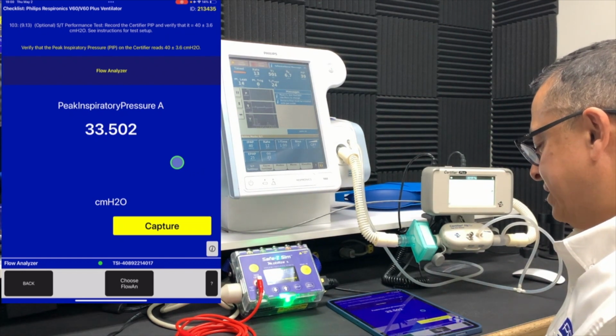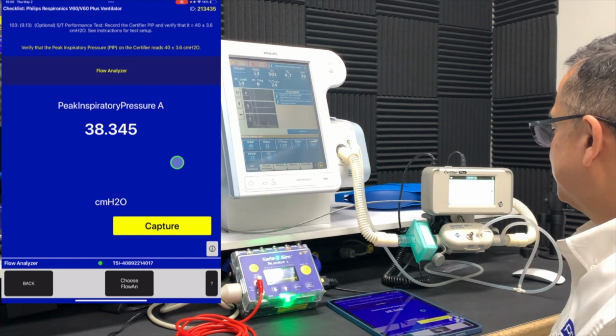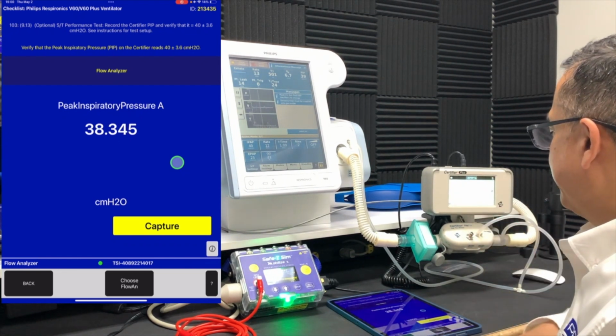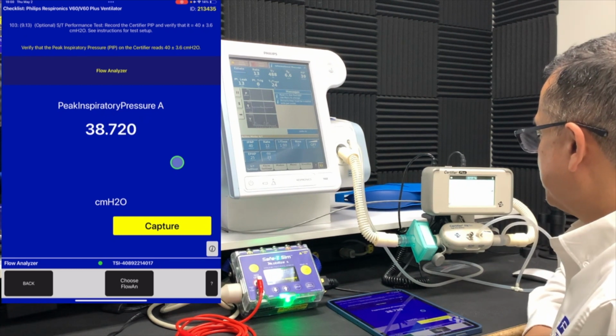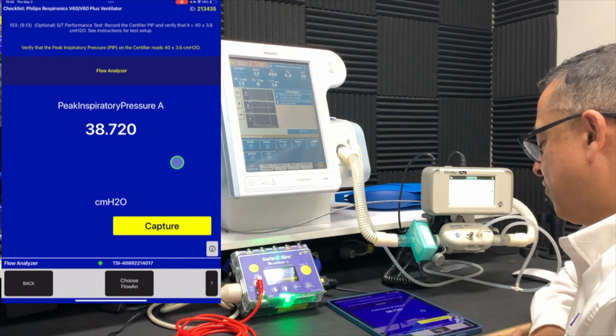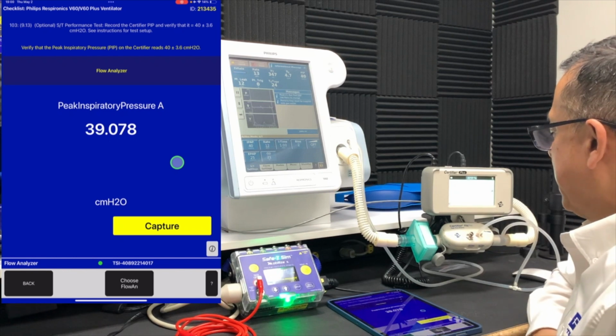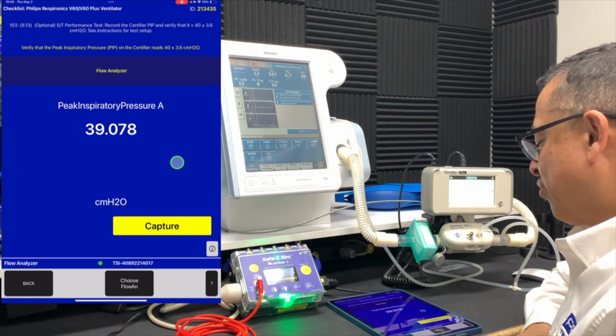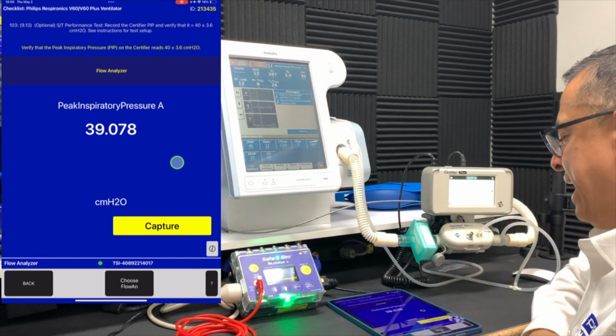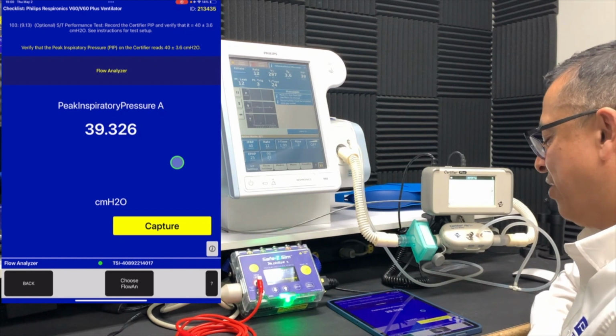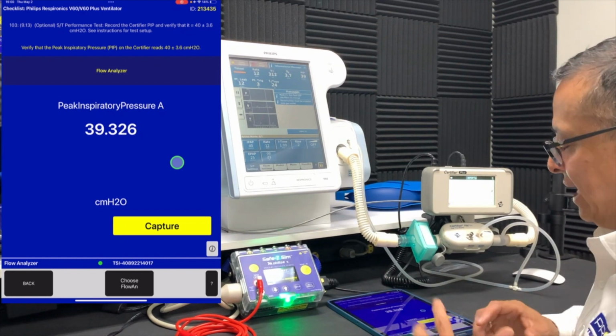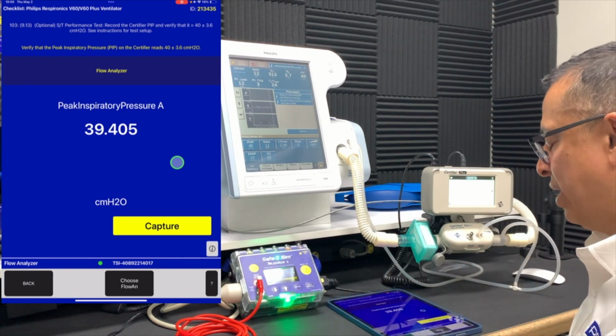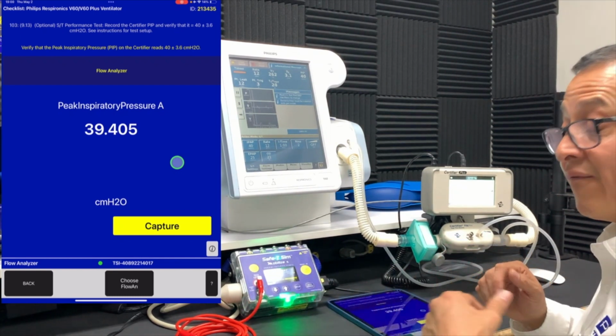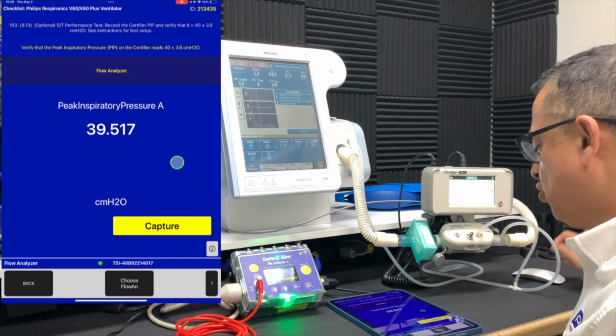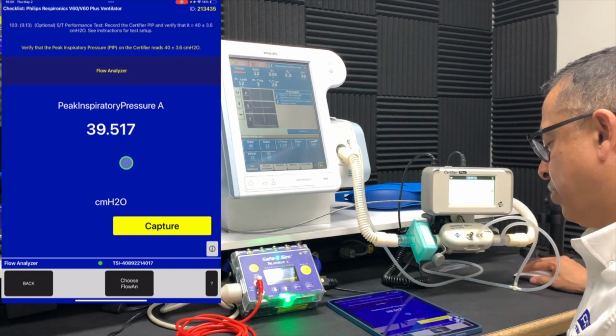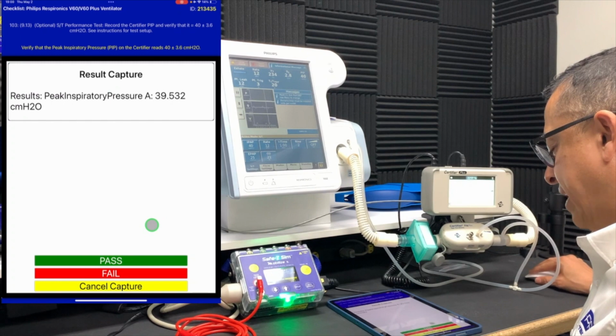And right now my analyzer is set to average based on 5 breaths, an average time of 2 seconds, which is also a requirement in the service manual. So we've also configured the sampling of the breaths for every 5 breaths. That's why it takes a little bit longer for you to get an average. As you see here, the average is now coming in within specification. Again, it's to make sure that you're not taking a momentary reading. You want to take a good long average to make sure your value is truly within tolerance. And you can see here, it's pretty stable now. We're going to capture that value.